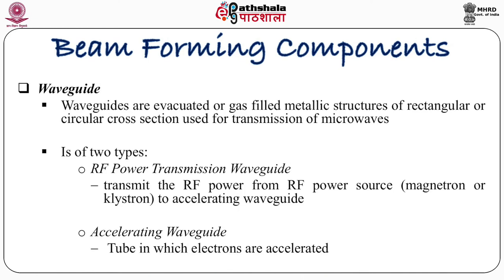The waveguide consists of evacuated or gas-filled metallic structures of rectangular or circular cross-section, used for transmission of microwaves. The waveguide is again of two types: the RF power transmission waveguide, which transmits RF power from the RF power source (magnetron or klystron) to the accelerating waveguide; and the accelerating waveguide, which is the tube in which electrons are accelerated. The RF power and electrons are synchronized, and electrons are injected into the waveguide. The energy of the electron is increased with this wave in the waveguide due to the klystron or magnetron, and achieves its final energy to produce photons or come out as an electron beam from the accelerator.